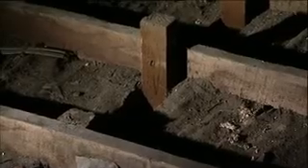Well, let's have a look, shall we? Okay. Well, there's nothing up here apart from a lot of dust. And no insulation means that Alan and Shirley are losing 25% of their heat straight through the roof. The government recommends that you use about 270 millimetres of insulation in a loft. And these days, most people are using about 300 in a new build. I reckon we should go with that.